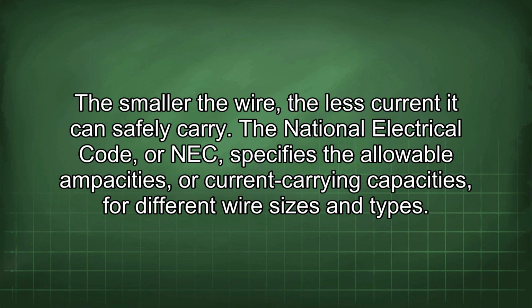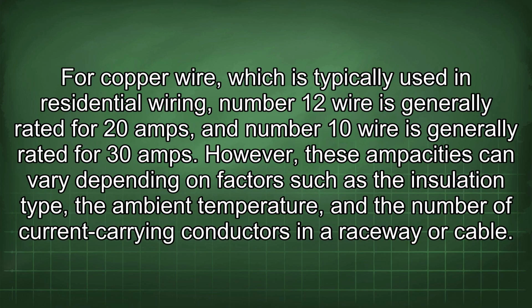The National Electrical Code, or NEC, specifies the allowable ampacities, or current carrying capacities, for different wire sizes and types. For copper wire, which is typically used in residential wiring, number 12 wire is generally rated for 20 amps, and number 10 wire is generally rated for 30 amps. However, these ampacities can vary depending on factors such as the insulation type, the ambient temperature, and the number of current-carrying conductors in a raceway or cable.